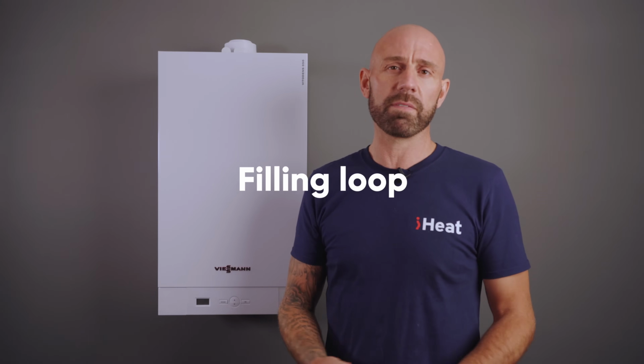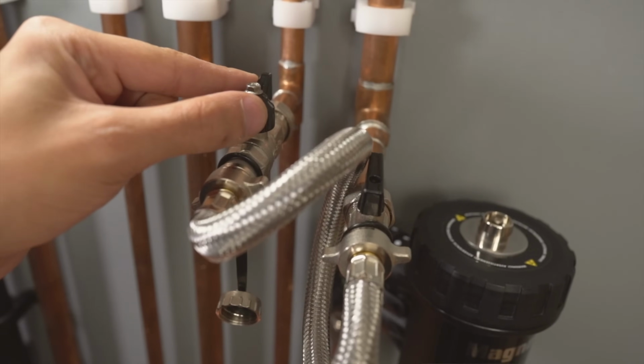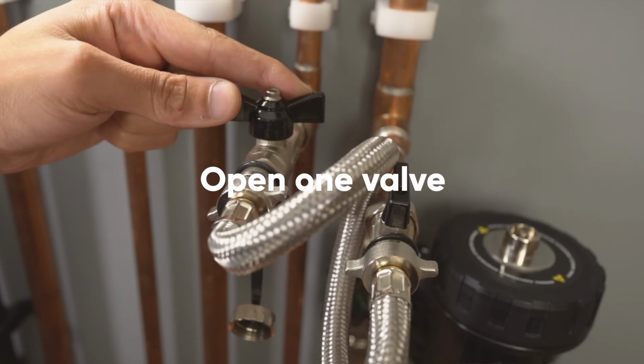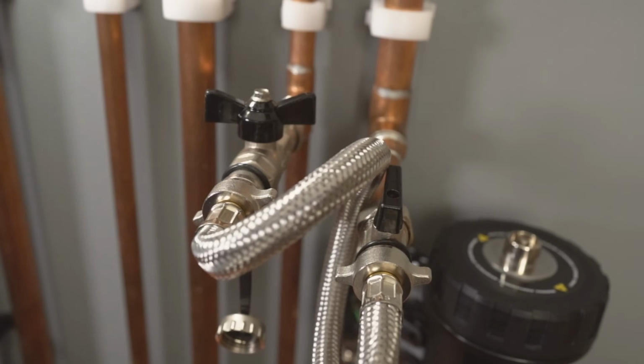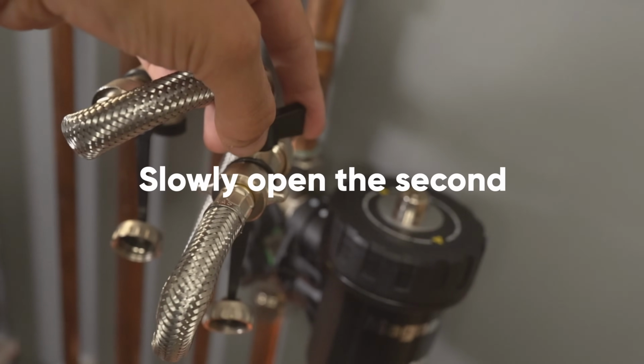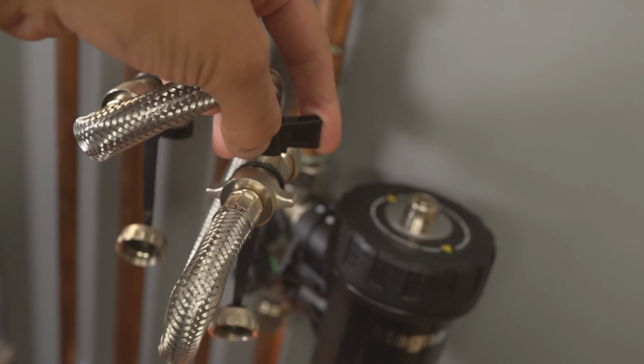Okay then, so you've found the boiler pressure gauge and the filling loop and have identified that the pressure is too low and needs topping up. If the filling loop is a typical loop pipe such as this one on the boiler, then first open one of the black valves on the filling loop. Then open the second valve. When doing this, you should instantly hear the water flowing through the pipe. Open the valve slowly as the pressure can rise quite fast.